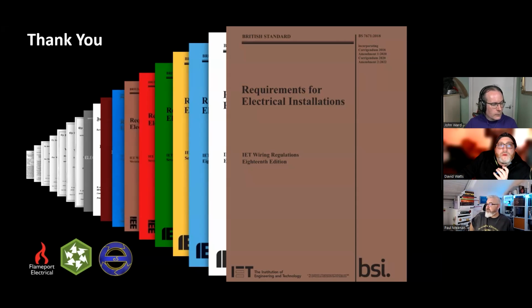Next question. Okay, actually, Ben's got a question which goes back to the TN system and the electrodes. So, can we not carry out a required test when carrying out, say, an EICR to check the difference between the installed TN system and the installed earthing electrode, to check for the difference that could be hidden that we discussed? The best way to do that would probably be like what you said, where you would break them down and measure them individually. Yes, you could.